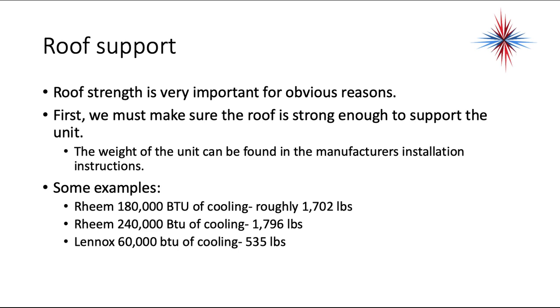Roof strength is very important for obvious reasons. First, we must make sure the roof is strong enough to support the unit. The weight of the unit can be found in the manufacturer's installation instructions. A few examples: a Rheem 180,000 BTU of cooling is roughly 1,702 pounds. 240,000 BTU of cooling can be up to 1,796 pounds. A Lennox system with 60,000 BTUs of cooling, 535 pounds. This is a lot of weight to be in one area of the roof, especially when there's always a little bit of vibration.